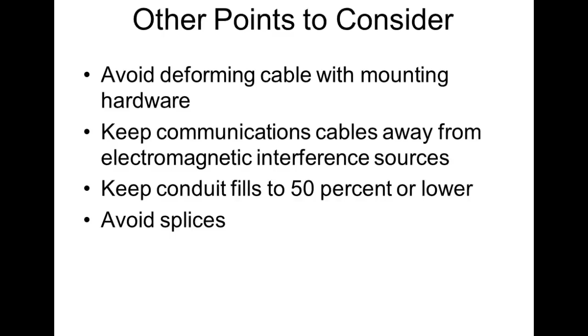And avoid splices. Normally when we pull communication cables, a lot of times we waste some cable, making sure we have enough pull to go from where we want to start to where we want to go. You'll see spools laid around because they don't try to use one spool until it's empty. They try to use one spool, and if that spool won't make the run, they get a new spool, but hold onto the other one for a shorter run. We don't like splicing these communication cables because it's real hard to keep a characteristic impedance through a splice.